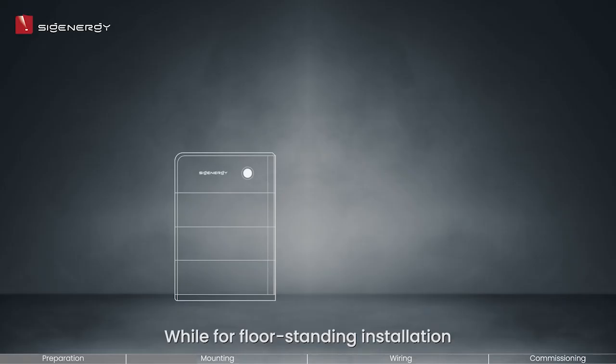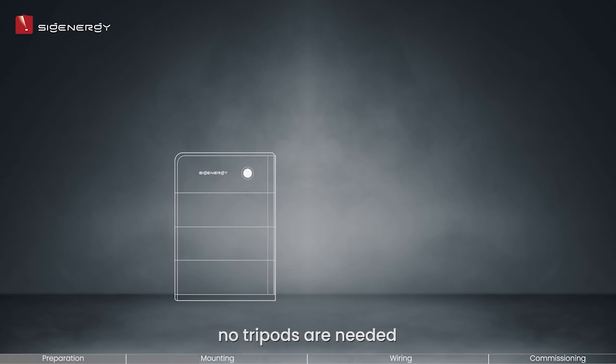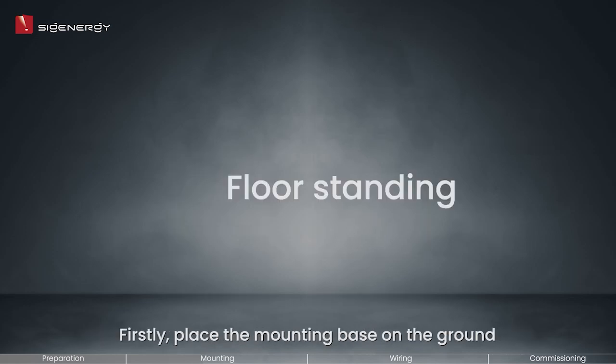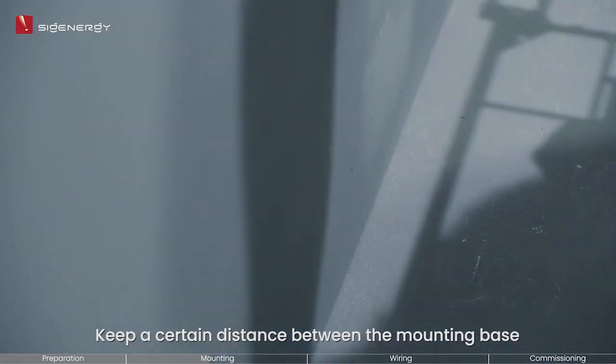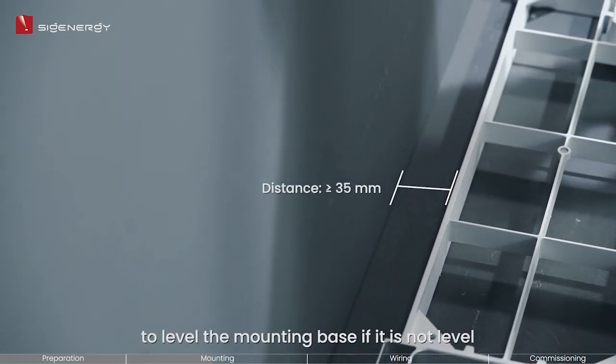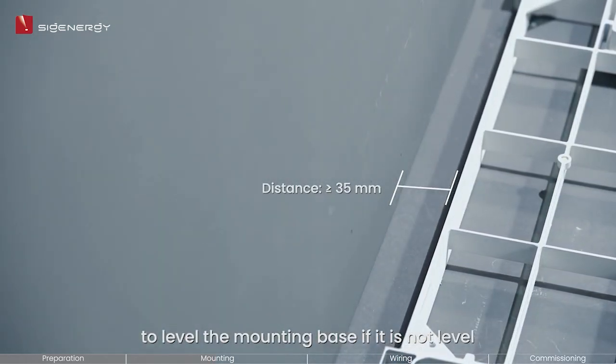For floor standing installation, no tripods are needed. Up to six Sigen batteries are supported for floor installation. Firstly, place the mounting base on the ground. Keep a certain distance between the mounting base and the wall surface. Use a supplied leveling gasket to level the mounting base if it is not level.